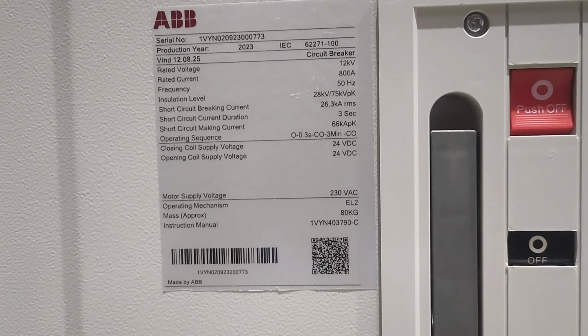For this we have to scan the QR here. I can show you the QR code that we have to scan. Generally, all the people are scanning the QR which is shown on the VCB door, but that is not the correct one. For the test reports, we have to open the door first. Then we can observe a QR which is mentioned on the CB nameplate, just like shown in the video. We have to scan this QR code for the test reports.